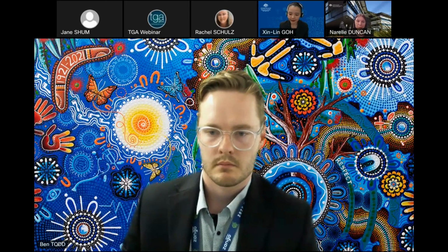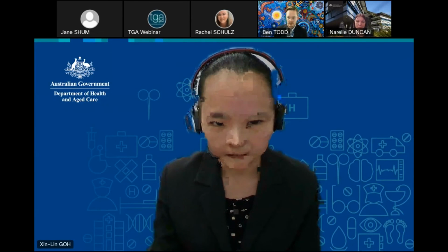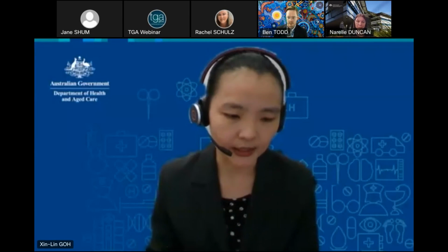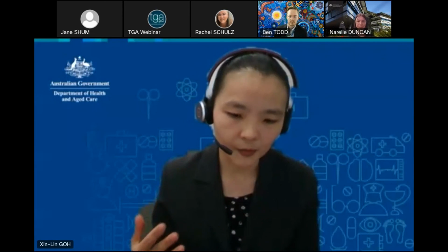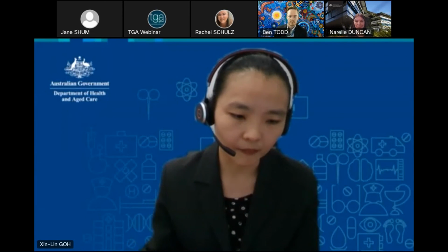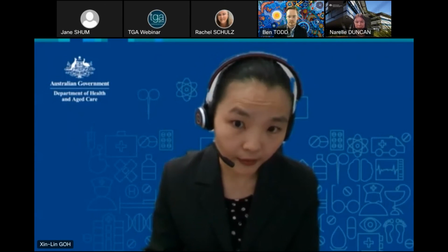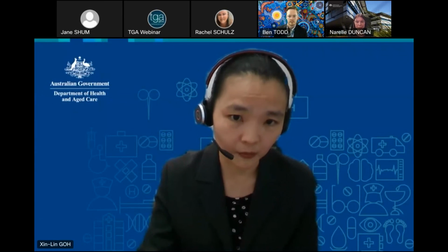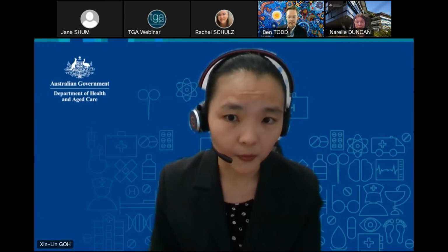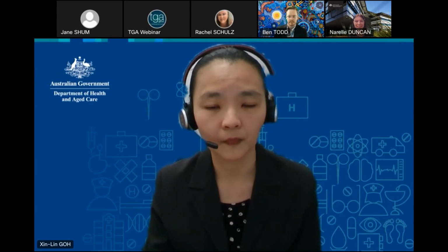So as Amanda outlined in yesterday's webinar, there is this clause in Europe, and we've adopted a somewhat similar position in that if your MDD certification is expiring and you have no valid certification thereafter, we expect sponsors to be ceasing supply at the 12-month mark, or within 12 months of your MDD certification expiring. So that is a very similar policy to what's happening in Europe. Thank you.